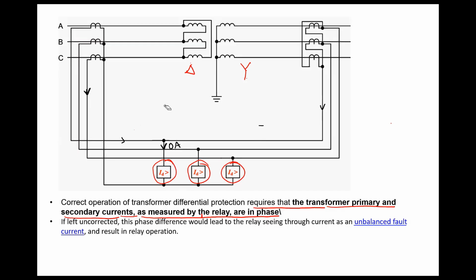If you don't properly choose the ratios, then the transformer will be continuously tripping. When you try to switch on the breaker, it will continuously trip, because there is a difference in magnitudes and phase angles, if you connect the current differential scheme like an ordinary element, like stator winding of a generator, bus bar, or motor winding protection.